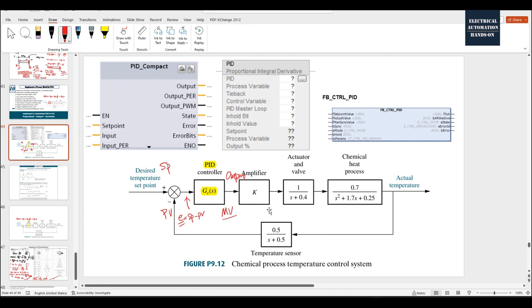While using the function block from each brand, we connect the setpoint variable to the setpoint input, and the process value — temperature, pressure, or water level — to the process value input. The control command is typically a value from 0 to 100, which can be connected to valve control. The valve is typically controlled by 4 to 20 mA using the analog output. So this is one typical PID: two inputs and one output.